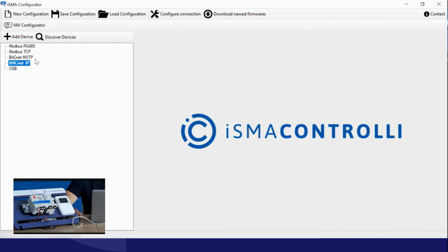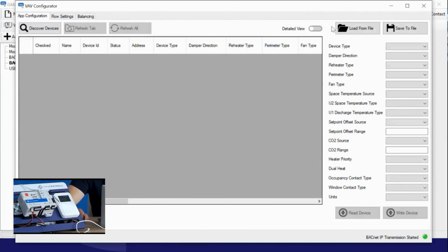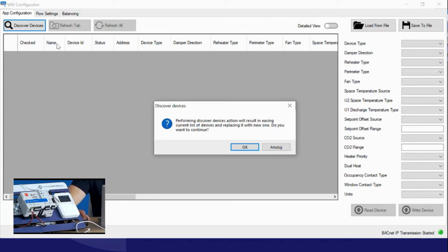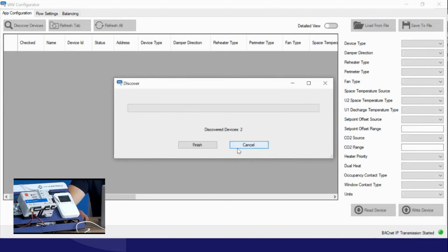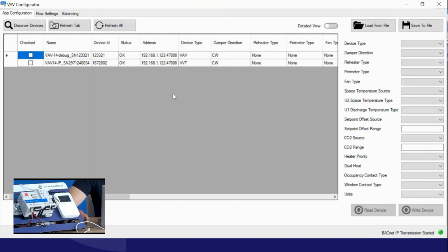And now, using the same software, I will open the dedicated menu, the VAV tab configurator. This tab allows me to discover all the controllers on the bus. So I just need the wire connection. I think this is important. We've done a one-to-one configuration, and now we change to a multi-device configuration. You can discover all your BACnet devices on the network and set them up directly from the iSMA Configurator, not just one by one, but from one tool, commissioning all the VAV units on the network. Exactly. And you can see that on my controller, I changed the VAV type from VVT to VAV.